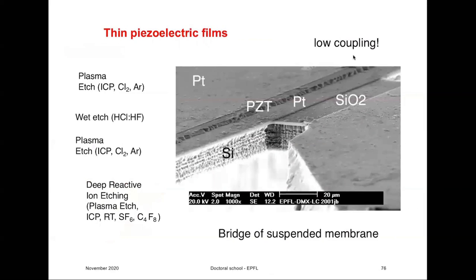Of course, one way to get these small elements is to use very thin piezoelectric films. And here is one. This is silicon. This is a platinum electrode, this is a platinum electrode, and between them there is a PZT element, which is just a few microns thick. The problem with this is that when you make thin films, you have to deposit them on some substrate. And when you drive a film, you will also drive the substrate. So part of this energy will be given into the deformation of the substrate.